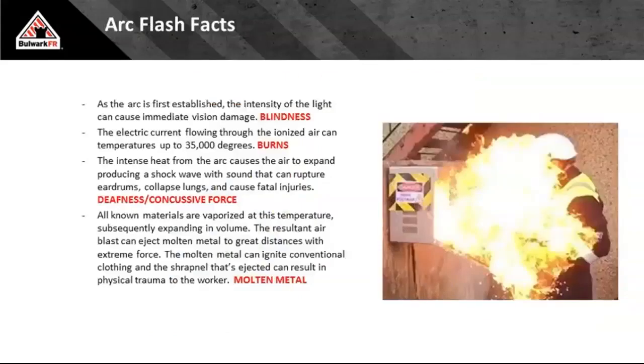So what are arc flashes? Real quick. There's been lots written on arc flashes. Most people know the numbers. Most people understand all that's going on. So just quick review. Depending on what periodical you're reading and how you're interpreting it, inside that arc gap, 35,000 degrees. Yes, about 2.5 to 3 times the surface temperature of the sun is created in that arc gap. 10 to 18 inches outside of that, you can argue, depending on which publication you're reading, anywhere from 5 to 10,000 degrees coming out of the box.